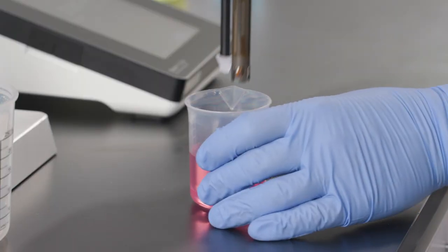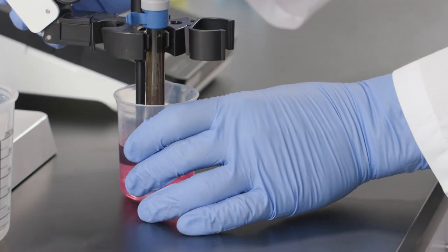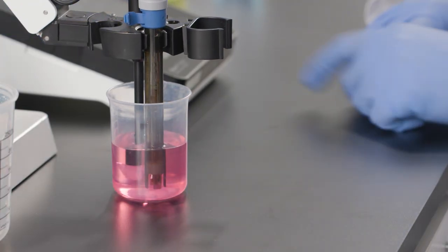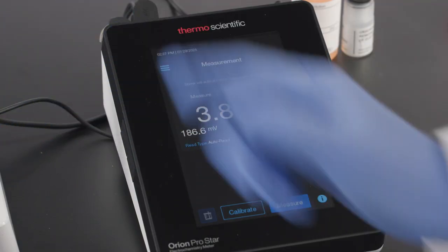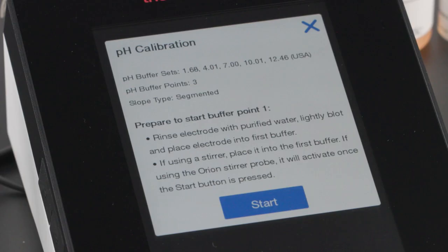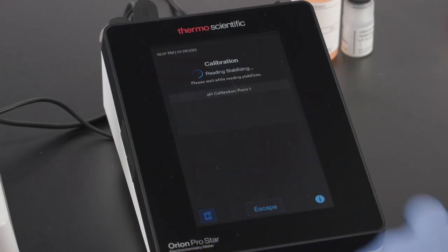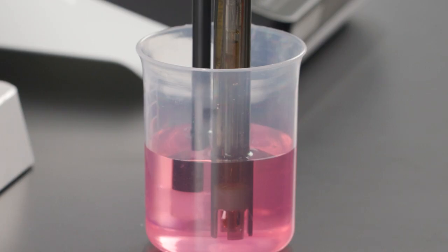Place the electrode into the first buffer. In this case, we're starting with pH 4. Then tap the Calibrate button on the meter. Instructions on the Orion ProStar meter screen guide you through the calibration. Tap Start to begin. When using a stirrer probe, stirring will start automatically. If you're using a magnetic stir and stir bar, start stirring manually now.